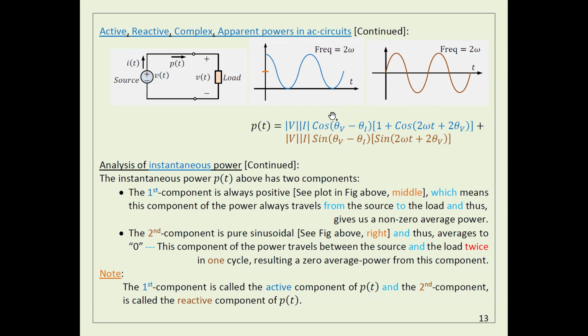And today, I will give you a very good example to understand why. I told you, when the power factor is very close to 1, that's what we want, right? That's very good, because by doing that, we can reduce the losses. This is just a verbal statement. I will show you a numerical example now of how this can happen. I will show you what happens at different values of power factor, and for every value, I will calculate the losses, just to confirm what I said. You can see we can reduce the losses as we make the power factor very close to 1.